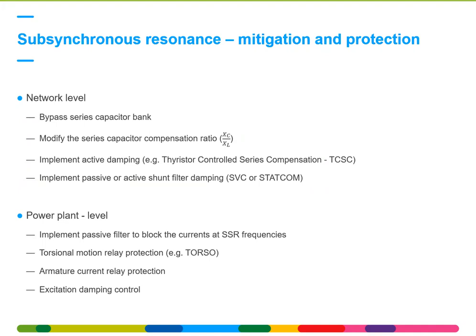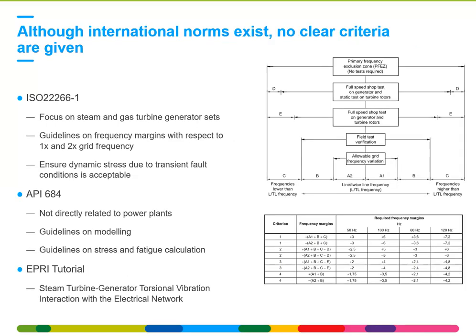On the power plant level, you can, for instance, implement a passive filter to block any subsynchronous currents that arrive at the power plant, or you could trip the machine by means of a torsional motion relay protection. So this is, for instance, the torso, which protects your machine, decouples it from the grid when an interaction with the grid appears, which could drive the system unstable and consume lifetime of your rotor. Other examples are armature current relay protection, so also based on the electrical measurements. So on the power plant level, typically what is implemented is an automatic trip based on measurements of the mechanical torsional amplitudes or the electrical parameters.